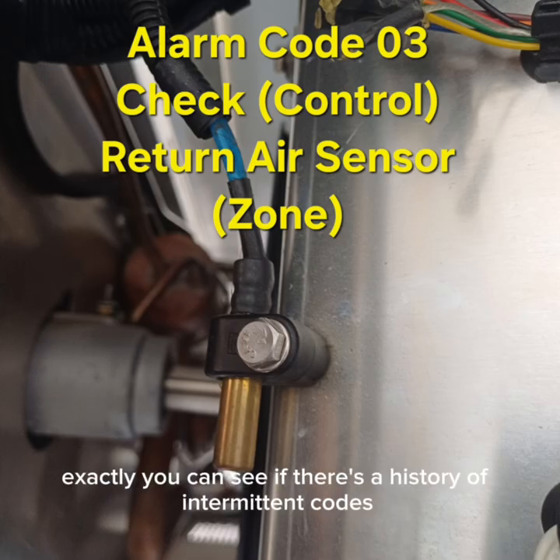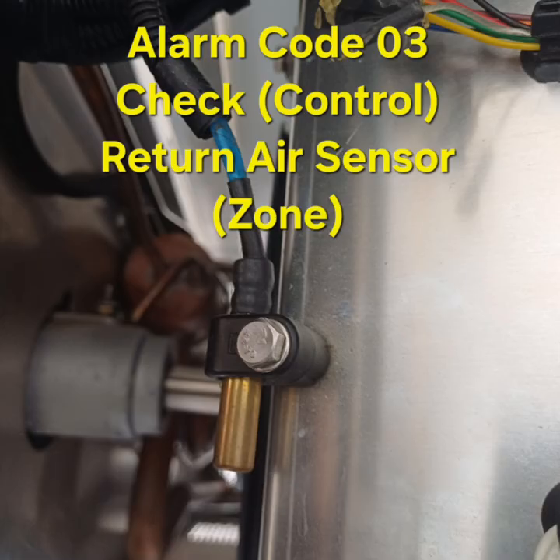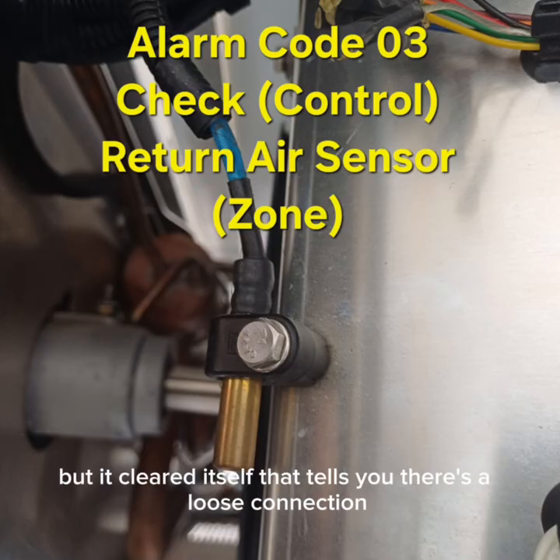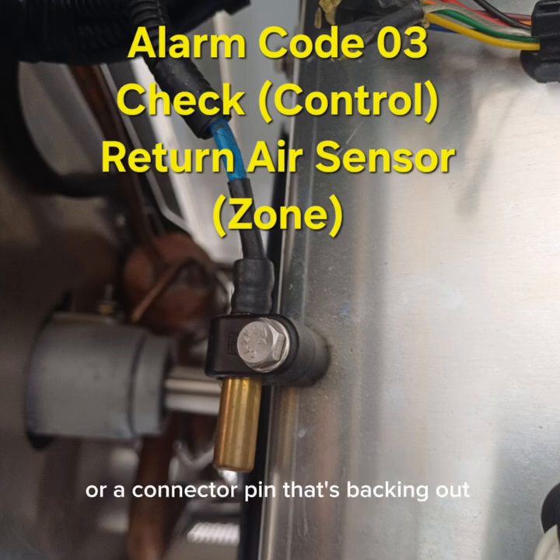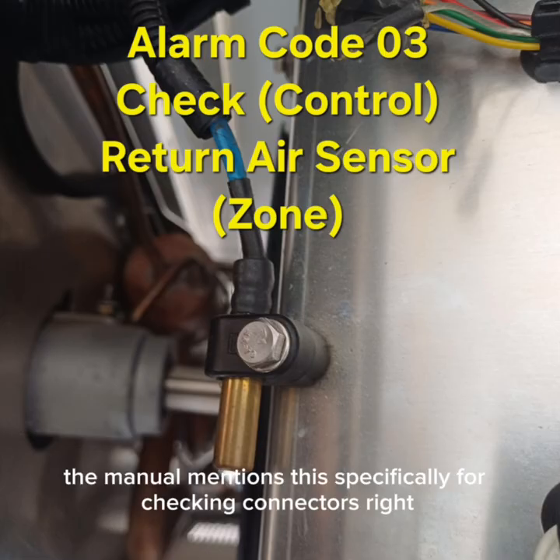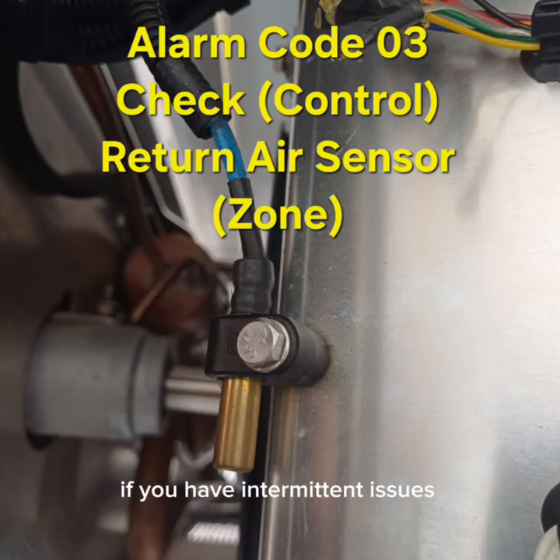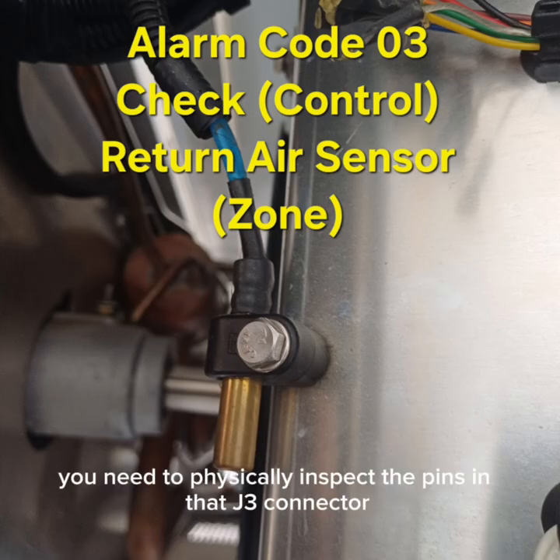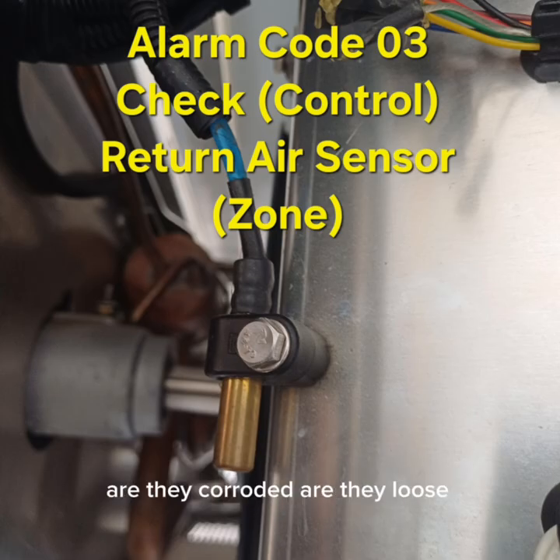Exactly. You can see if there's a history of intermittent codes. Maybe this unit has thrown code 03 5 times in the last month, but it cleared itself. That tells you there's a loose connection or a connector pin that's backing out. Which brings us to service procedure D01A. The manual mentions this specifically for checking connectors. Right. If you have intermittent issues, those are the worst ghosts to chase. You need to physically inspect the pins in that J3 connector. Are they corroded? Are they loose? The data log tells you when it happens, which helps you figure out why.